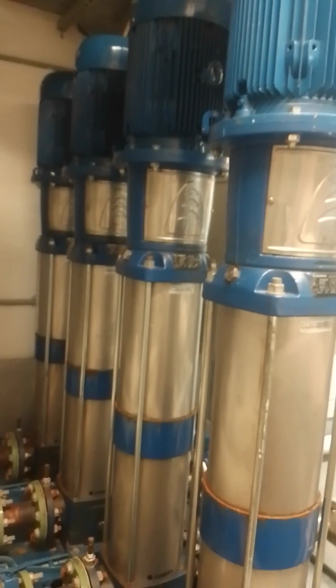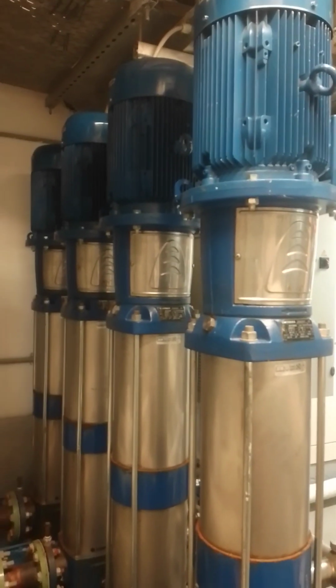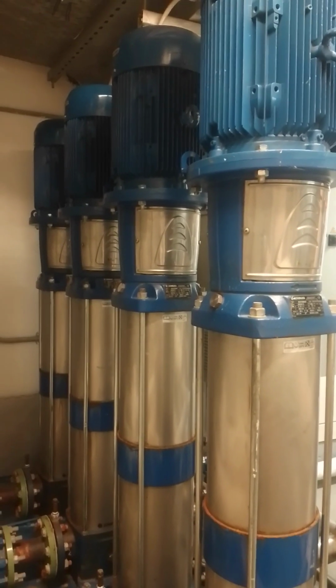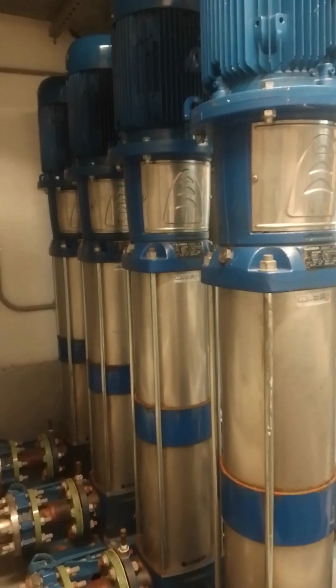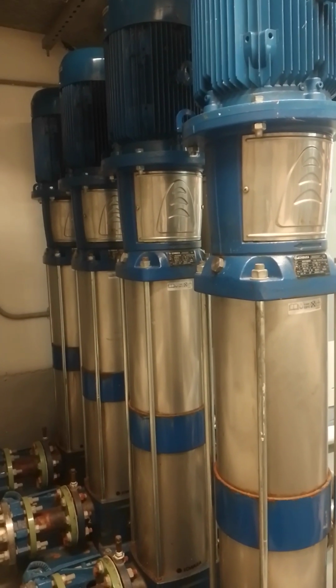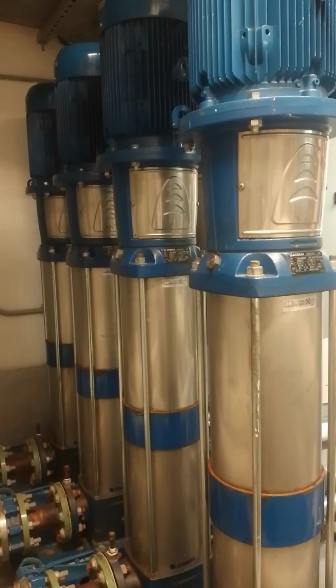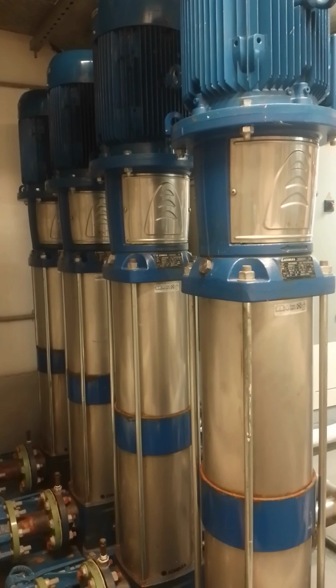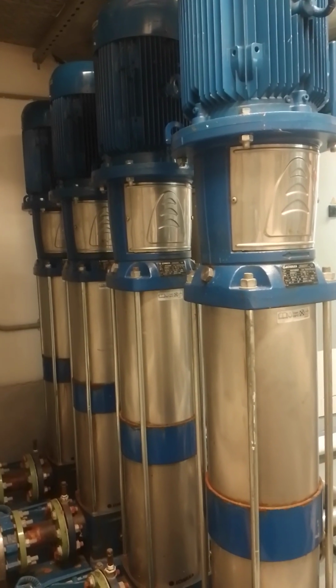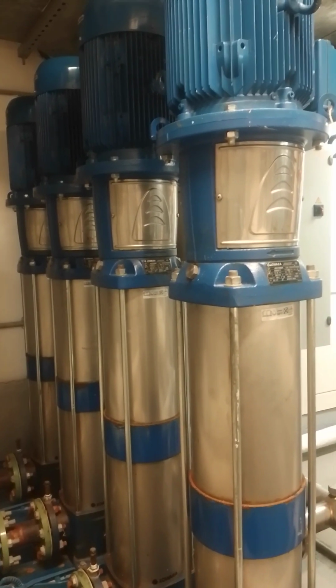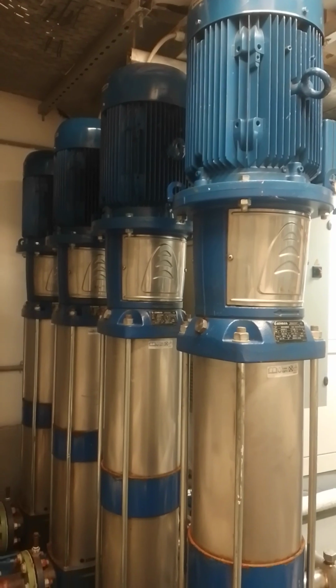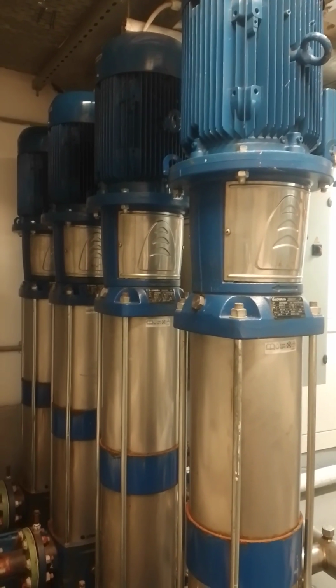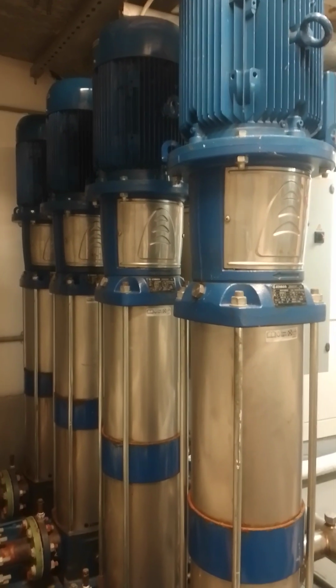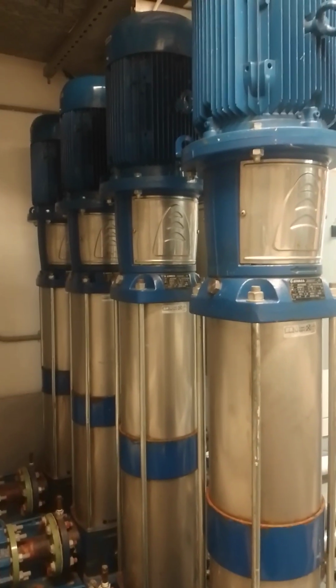If more pressure is needed, it can switch on 2 or 3 pumps simultaneously, one by one. If it's running one and it went off, then when there is another demand, it will not start from the one which was off, it will start the next. So it is set like that.